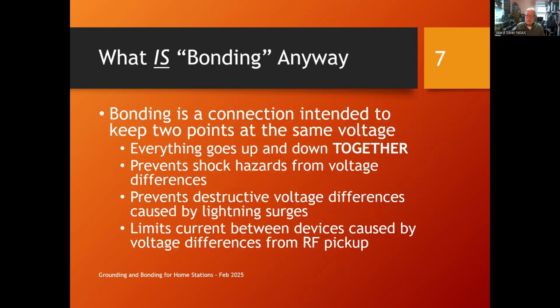Bonding, if you look it up, is a connection intended to keep two points at the same voltage. That's it. No fancy definitions and sub-definitions and qualifications and all that kind of thing. It's just a connection between two points to keep them at the same voltage. If you do that, they're called electrically bonded. The whole point of bonding in your station is so that everything in the station goes up and down together. And you'll hear me talk about this all the time. Everything going up and down together, either because of RF pickup or because of AC fault current or because of a lightning strike nearby. When everything goes up and down together so that it's at the same voltage, that prevents shock hazards from voltage differences.